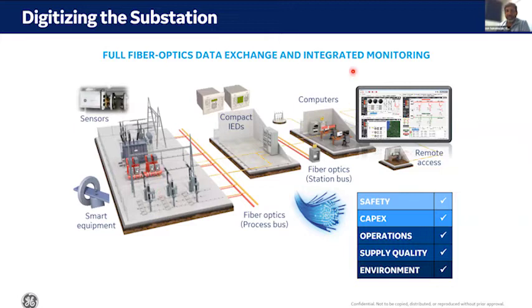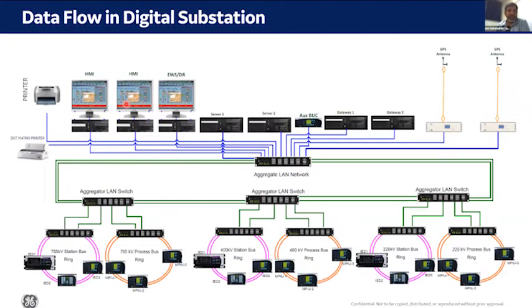Since we are digitizing information right from the process side, we get more information in terms of monitoring, supervision, and situational awareness. In one recently proposed project architecture, you can see the process bus ring and the station bus ring at different voltage levels — all redundant. Whether it is the station bus or process bus, availability has improved. Earlier, the CT core connection went directly to the relay as a single connection; now redundancy is built into the communication media itself.